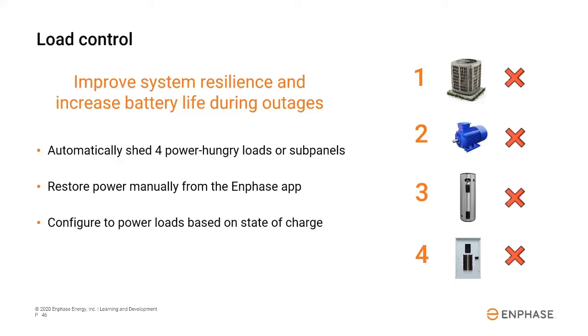It can also be configured to power specific loads based on the state of charge, or how much energy remains in the battery. So this can be useful if someone wants to run their air conditioner in the afternoon to cool their home down, but they want to make sure they don't completely deplete the battery. So for example, once it gets down to 30%, power can be disconnected from that appliance. And then on the other side of the coin, once the system is recharged by solar the next day up to a certain level, then power can be reconnected to that appliance.